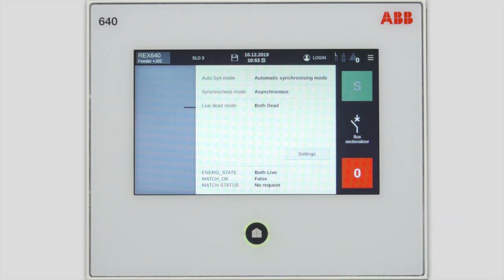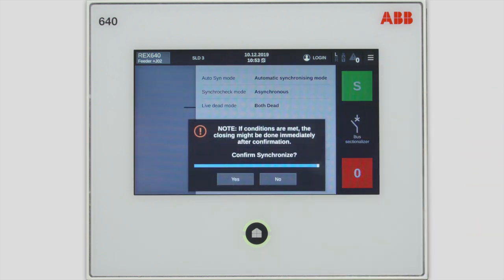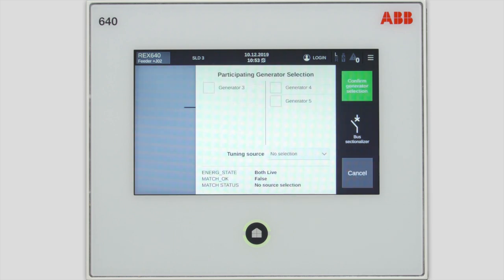When the selections are stored, you can continue with the actual synchronization by tapping S. You get a prompt referring to the situation where the synchronization conditions are already met, and the breaker will close immediately once you confirm the synchronization. In this example, the next step is to select which generators participate in the synchronization. The target is that one side of the bus sectionalizer remains as a reference, the fixed side, and the generators on the other side will be controlled.